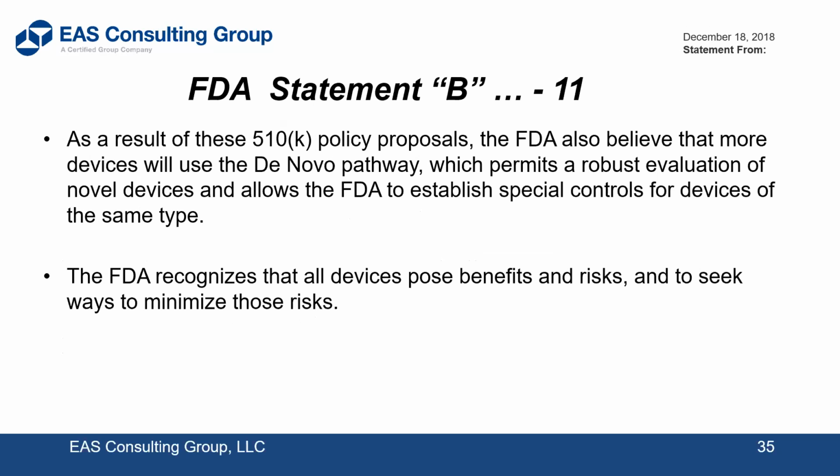It also mentions that where in the past de novo was almost never heard of, now it's becoming a little more prevalent. It's kind of the in-between of the 510K and the PMA. It takes a PMA device that has a low safety issue, and you can go the de novo route. And then once the de novo product has been cleared or approved, it becomes a predicate device for future 510Ks, not de novos. So that's it, and I'm working with one client on that right now.